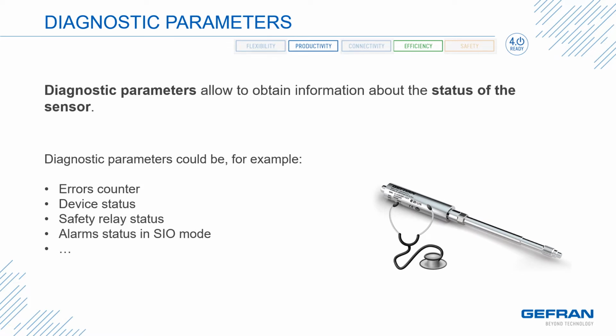There are several diagnostic parameters available, such as an error counter, device status, safety relay status, alarm status in SIO mode. SIO is standard input-output mode, which is the basic operation of the sensor before it goes into the IO-Link mode.